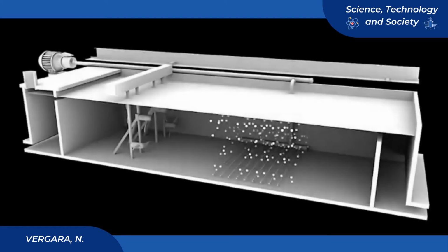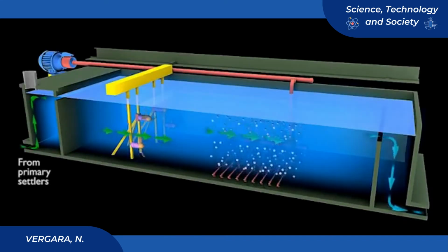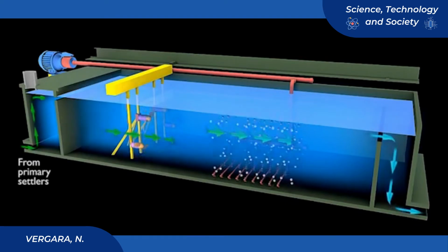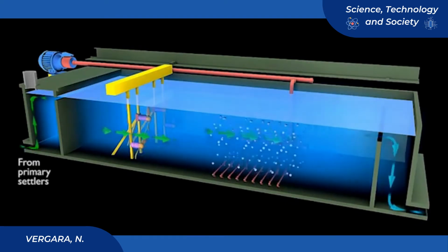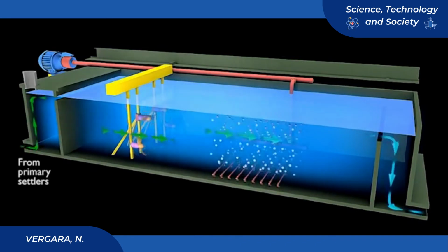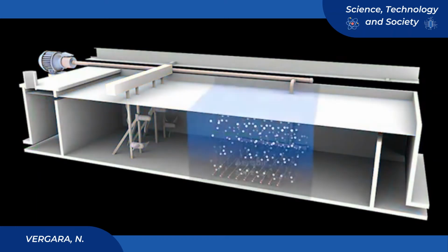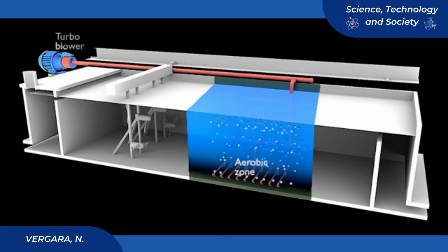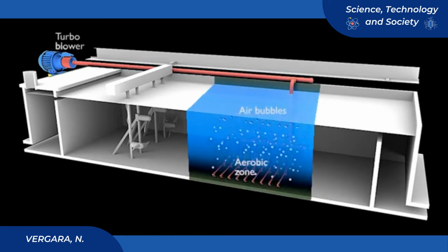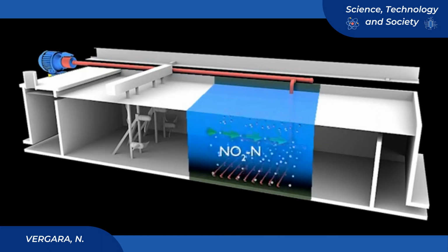Secondary treatment is the heart of the wastewater treatment process. Whereas the previous steps of treatment consisted in removing the suspended solids by settlement, this step of treatment consists in removing the major part of dissolved pollution, mainly BOD5 and ammonia. During the aeration phase, specific bacteria eat the dissolved organic matter and transform it into suspended solids. Other specific bacteria oxidize the ammonia into nitrites, then nitrates.